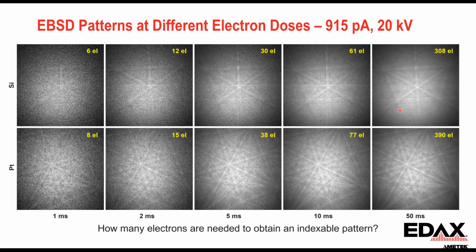That's just a result of counting, the Poisson noise kind of thing. When we talk about this being a noiseless detector, we're talking about cutting out the electronic read noise of the detector. We'll still have statistical noise from the number of electrons that are counted. As we count more electrons, the bands become more apparent to the eye, but you'll also see that on these low dose conditions, we can see patterns that would not be visible at similar doses with a camera that did have read noise.